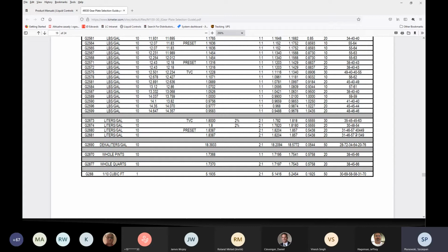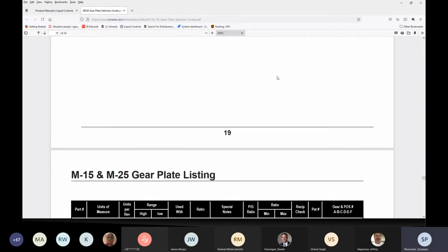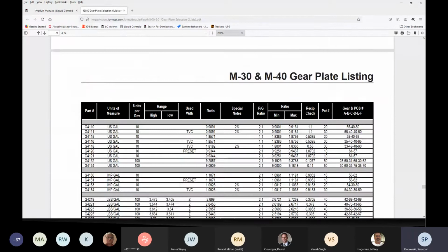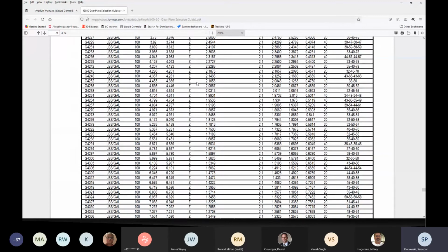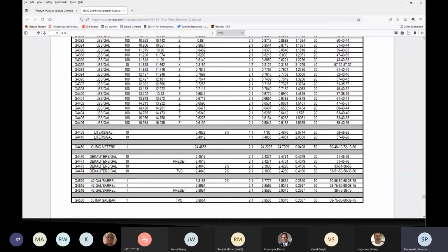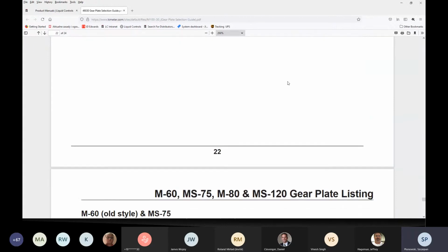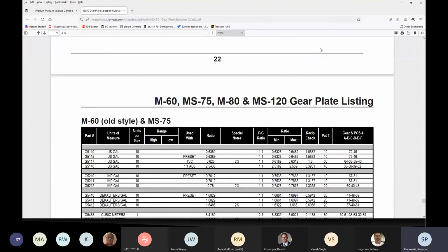And also, if you decide to build your own gear plate, it gives us the 3 gears that go into this plate, which are gears of size 31, 46, and 57. The last number is just a reference drawing number, so it's not important. But those are the 3 gears that go into this gear plate. So again, it's a big manual with a lot of information. I just scroll through it, and you can go through meter sizes and find pretty much any gear plate that you would need. Now, again, just a word of caution: if you're not sure which to use, just give us a call. But this gives you a pretty good reference.